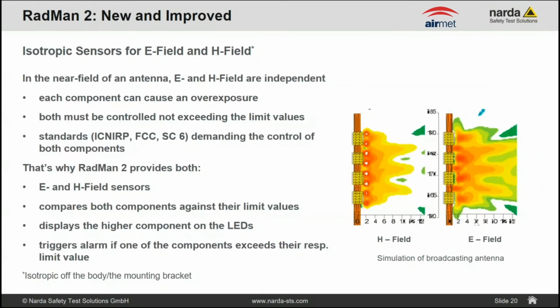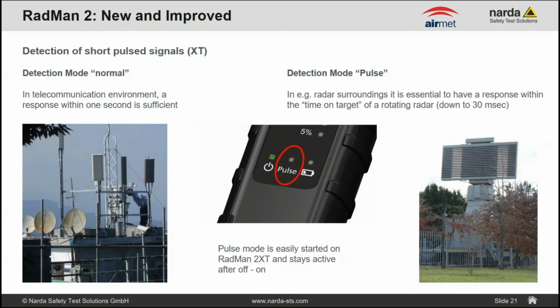For the sake of time, we have already used half of the time. I will speed up a little bit, but anyhow, you will get a copy of each and every slide provided by airmet. So the detection modes which we offer with the XT model in the new RadMan are the normal detection mode and the pulse detection mode with a faster, shorter integration time. Instead of 1 second, you can select 30 milliseconds, so that you are alarmed fast enough if there is any pulsed signal like radar.